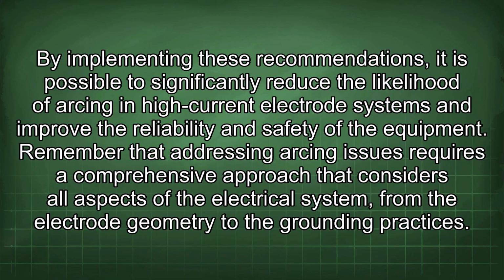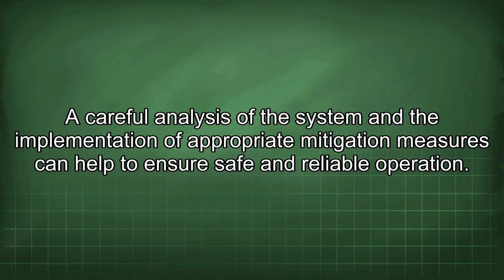By implementing these recommendations, it is possible to significantly reduce the likelihood of arcing in high current electrode systems and improve the reliability and safety of the equipment. Remember that addressing arcing issues requires a comprehensive approach that considers all aspects of the electrical system, from the electrode geometry to the grounding practices. A careful analysis of the system and the implementation of appropriate mitigation measures can help to ensure safe and reliable operation.